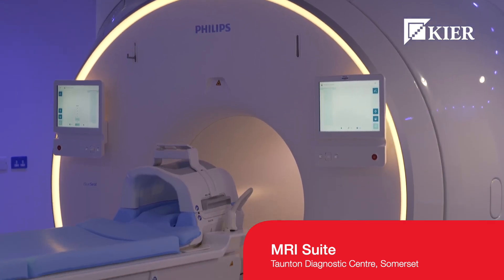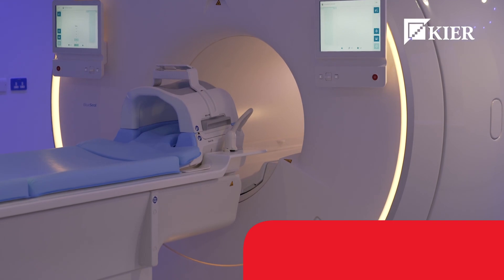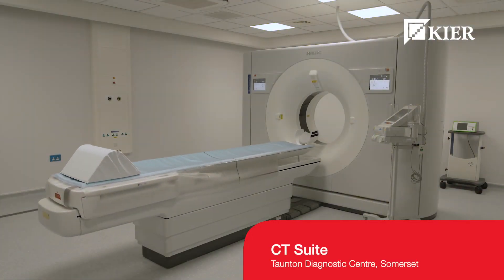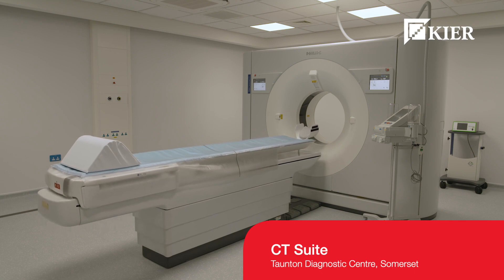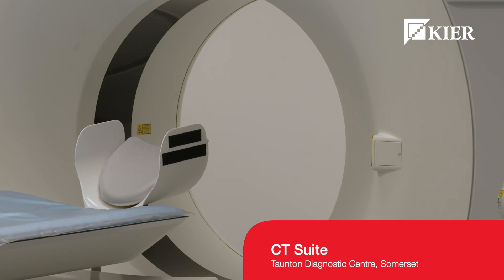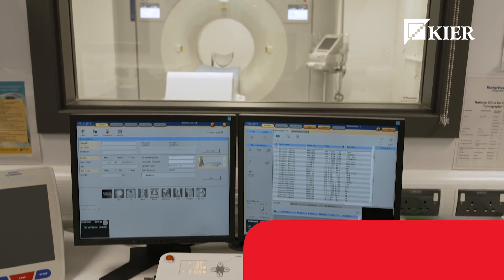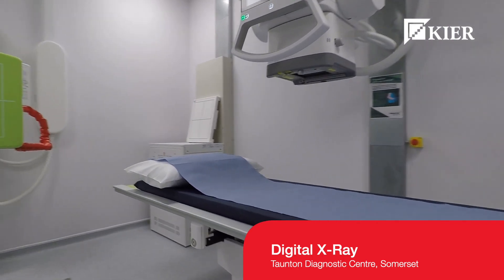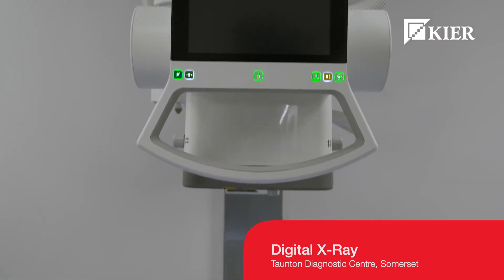We've effectively gutted the ground floor and then built up the slabs. There was a hell of a lot of services that we had to bring down through the building and around the building to serve the ground floor — some specialist equipment such as medical gases, various nurse call systems, chilled water serving the MRI, and high spec ventilation. We had to fit all that into very tight spaces within an existing building, so the design, installation, and builders work was very complicated throughout.